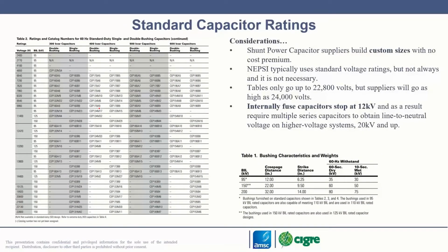One of the things that's interesting to note is that when you go to the capacitor supplier, you do not need to pick one of the standard capacitors. Here we're showing standard ratings of 300, 400, 500, 600. If you're doing filter design and you come up with a value of 575 kVAR at some funny voltage, give that to the capacitor supplier and tell them that's what you want. They'll come back and give you that design, and you're not paying a premium for it. It's something you realize after a while: just pick the values you want.